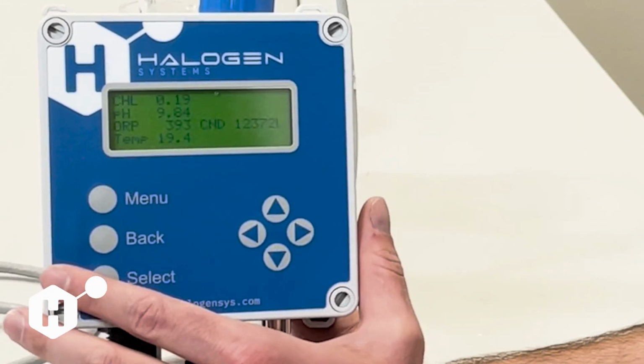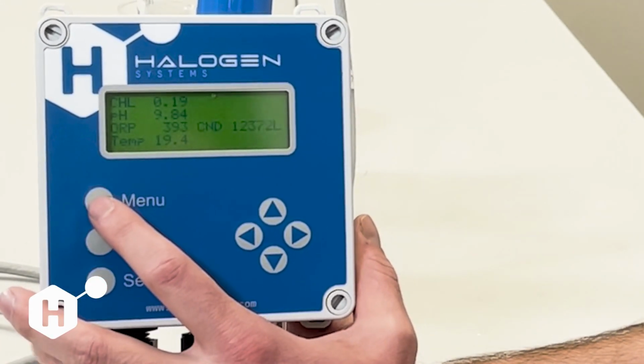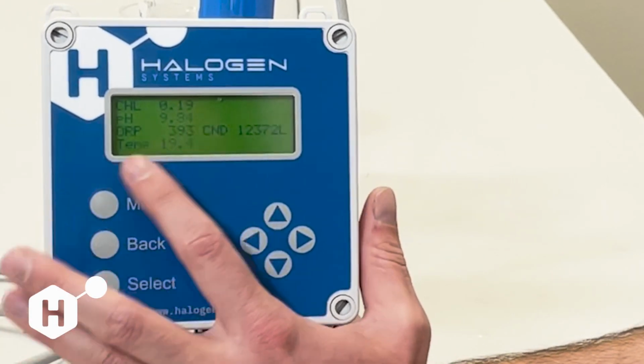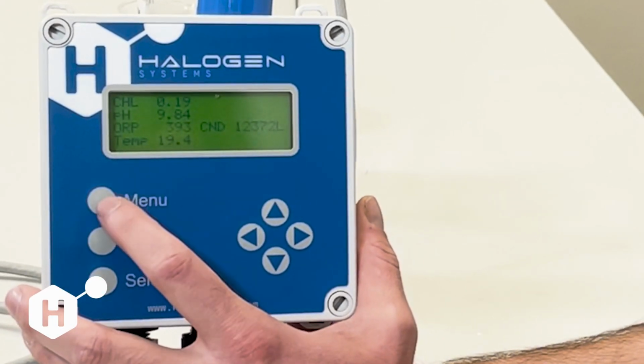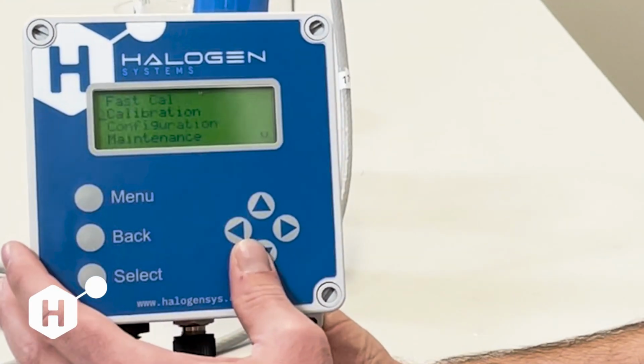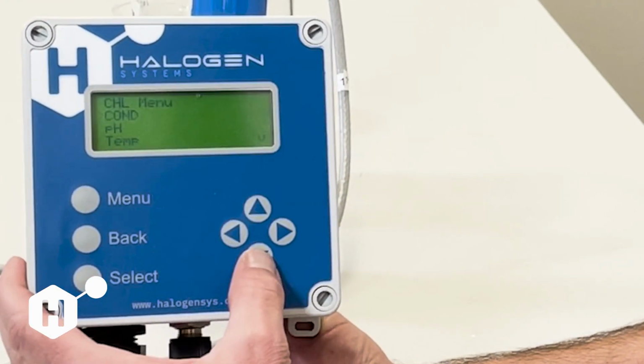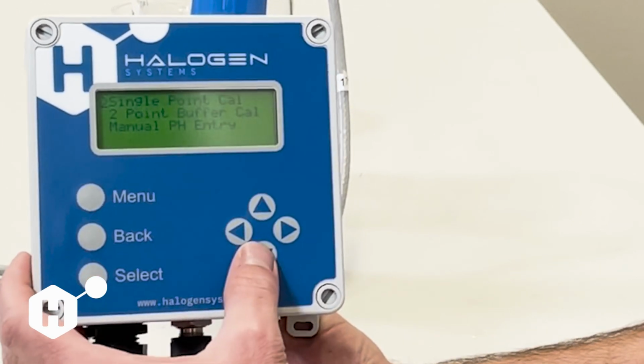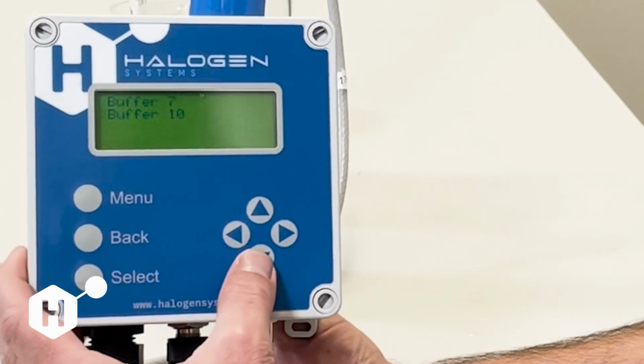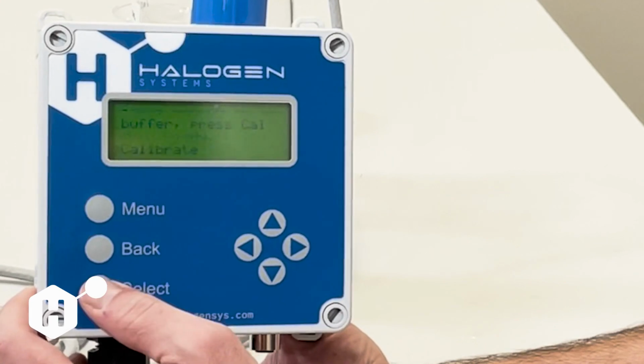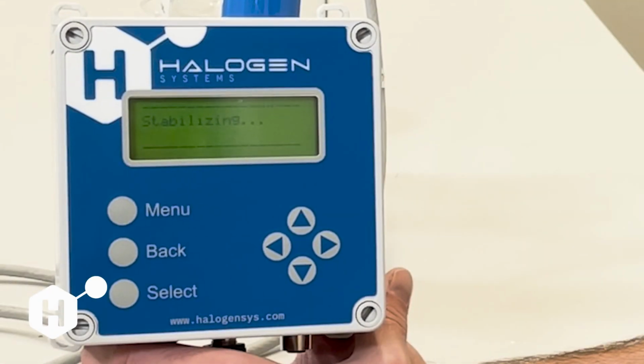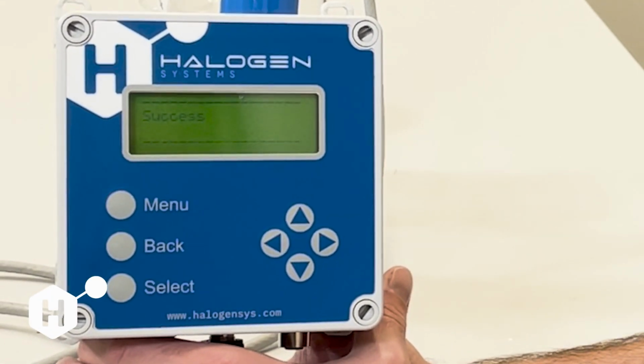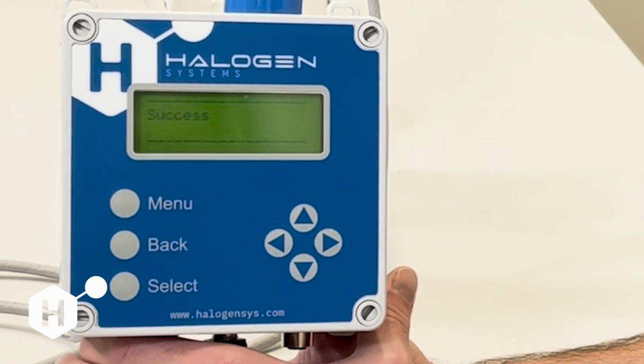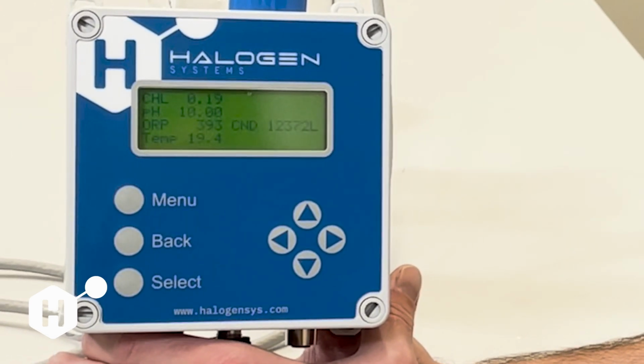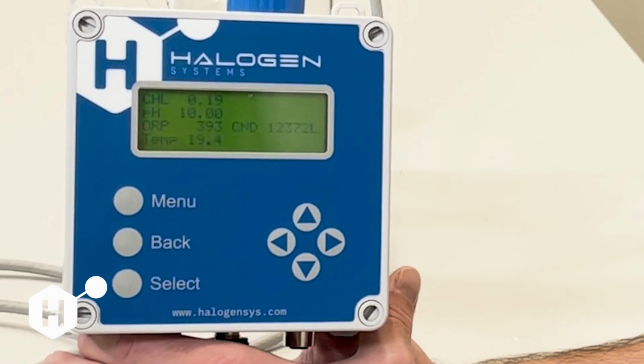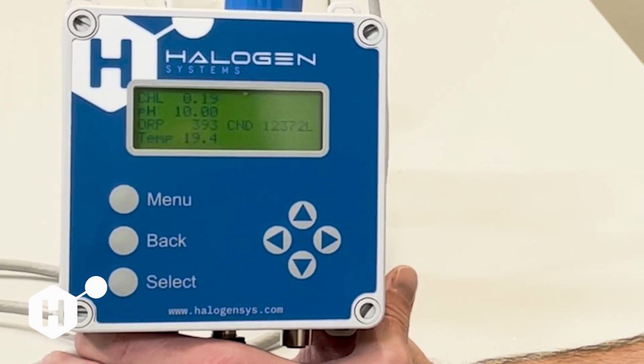If you're not happy with your calibration, you can always repeat the calibration while the sensor's still running in there. In this case, 9.84 is not quite where I want it to be, so I'm going to go ahead and do that calibration again. Doing repeats of calibrations does not hurt sensor calibration at all. It's actually more likely to be a better calibration the more you repeat it, because the longer the sensor has to stabilize, the more confident we can be in our sensor measurements.